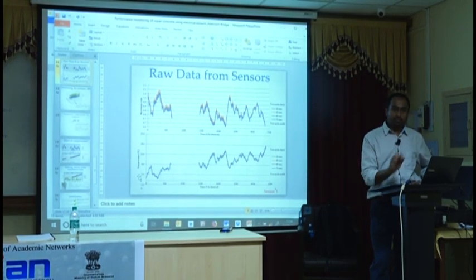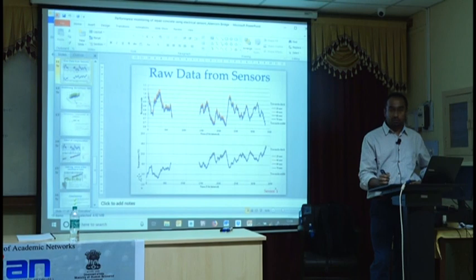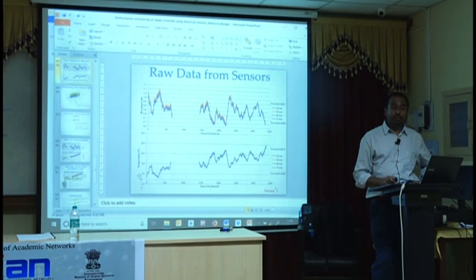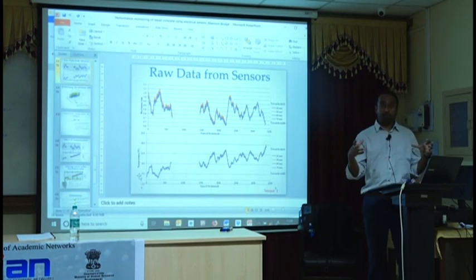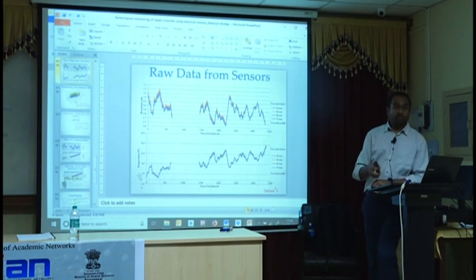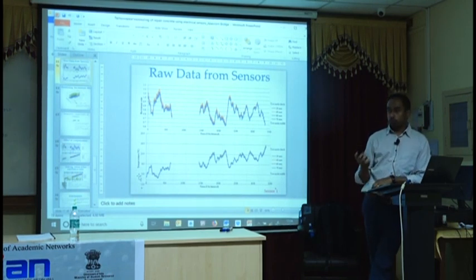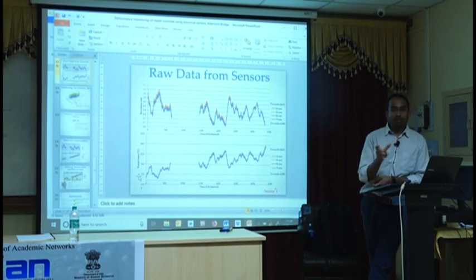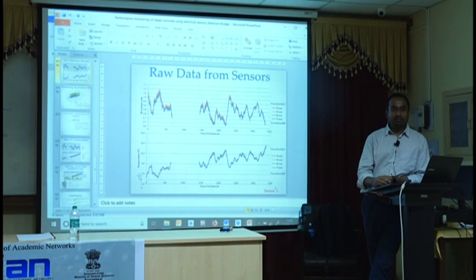You should, yeah. That's all part of the construction sequence and construction technique. So my suggestion would be to test it out and see what strain. If you put it on a strong metal plate, change the temperature and then see if it moves, if it gives you a strain value. If it does give you a strain value, that's your compensation coming in. I presume the supplier is doing that kind of compensation study.